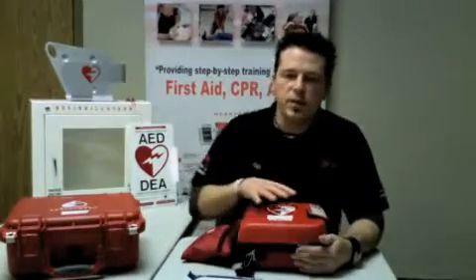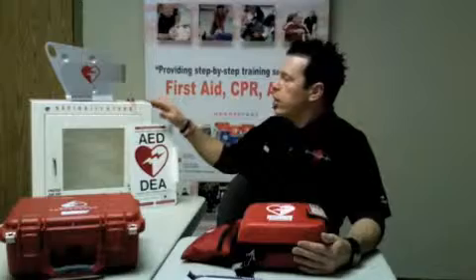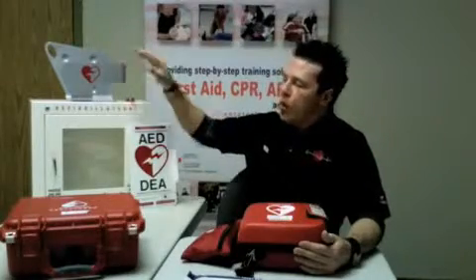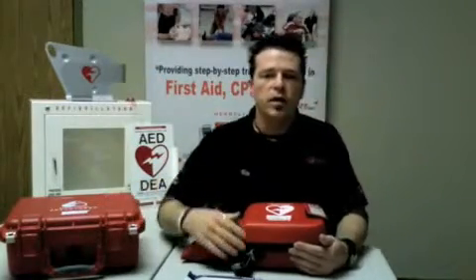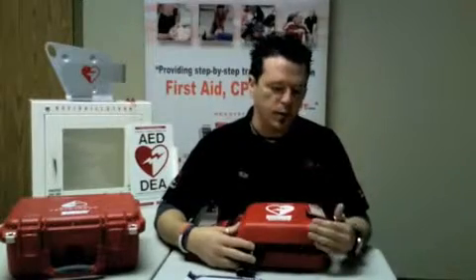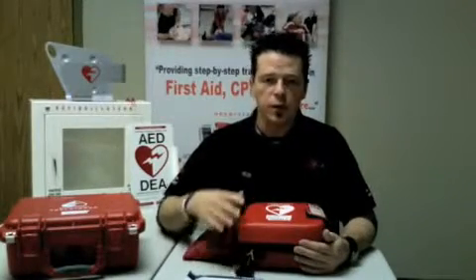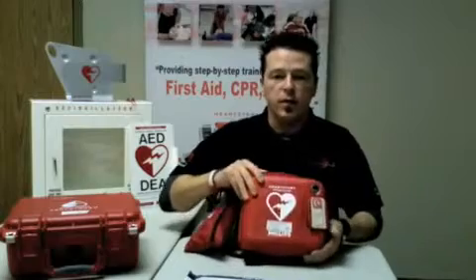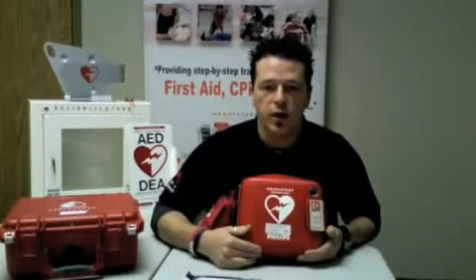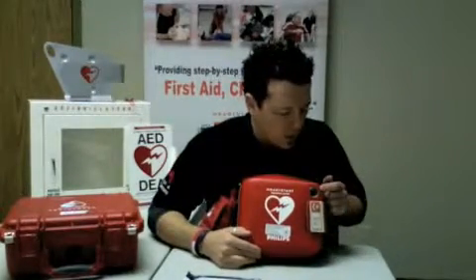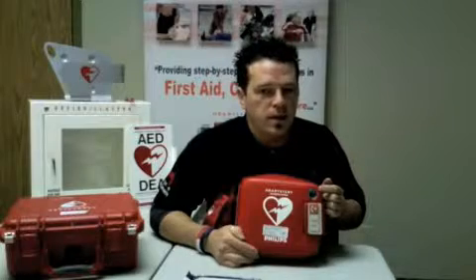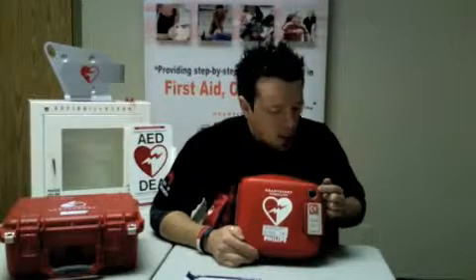Now, once you access the defibrillator, whether it be through the alarm security box, the wall-mounted bracket, or the Pelican hard case, there are a few things to keep in mind before accessing the defibrillator from the soft case. The first of which is to make sure that the defibrillator itself is currently in working order. In the upper right part of the soft case, you'll notice a little window, and if you look closely, there should be a flickering green LED light that does so every 4 to 5 seconds, which basically signifies that the defibrillator itself has passed its last diagnostic test.